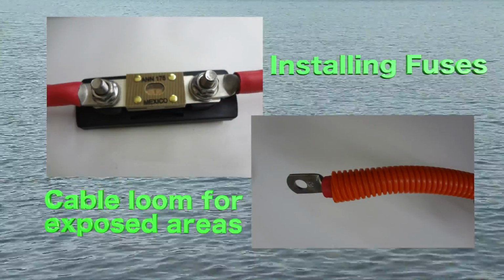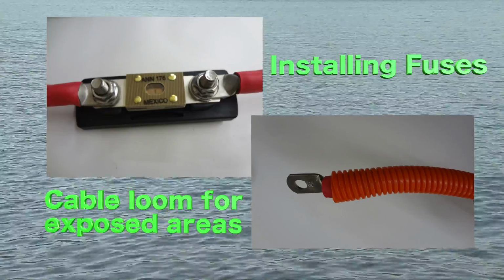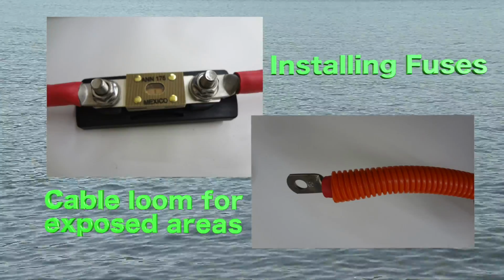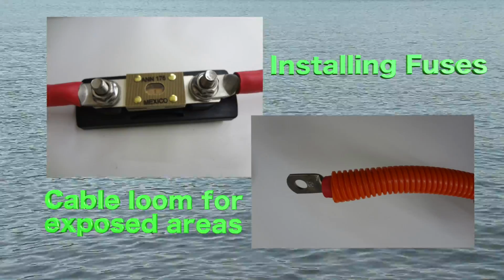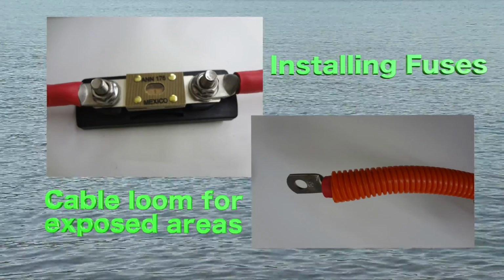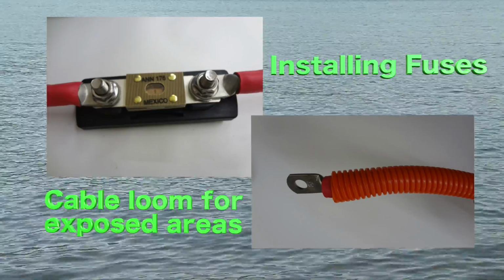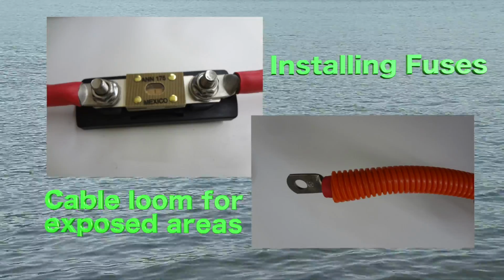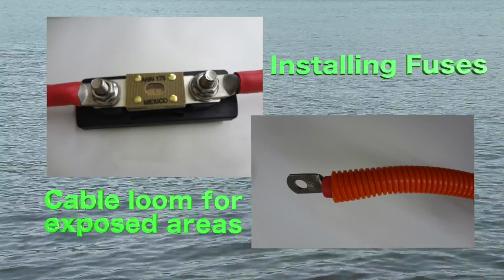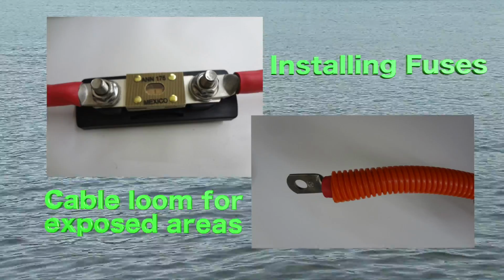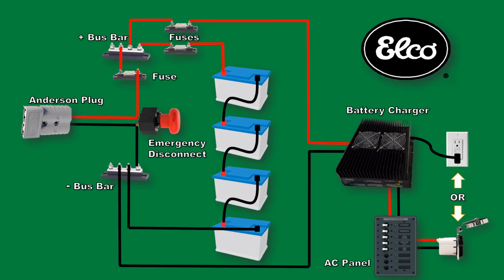Fuses must be installed in the circuit to protect against accidental shorting and for safety. Elco recommends using marine-grade inline fuse blocks like this one, securely mounted in a safe and accessible location, and as close as practical to the positive battery conductor, which should be protected by a sheath or cable loom in exposed areas. Circuit protection is needed in 3 places. First, a fuse is installed between the plus bus bar and the battery string. If more than one string is used, a fuse is installed for each.